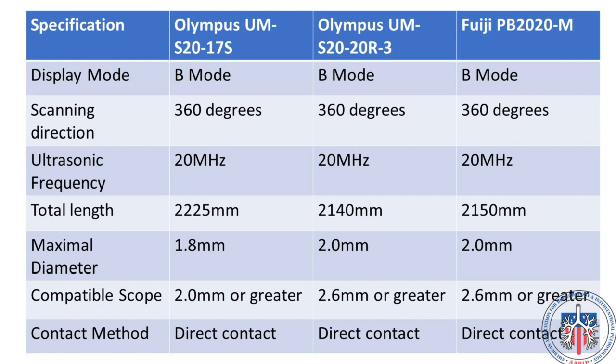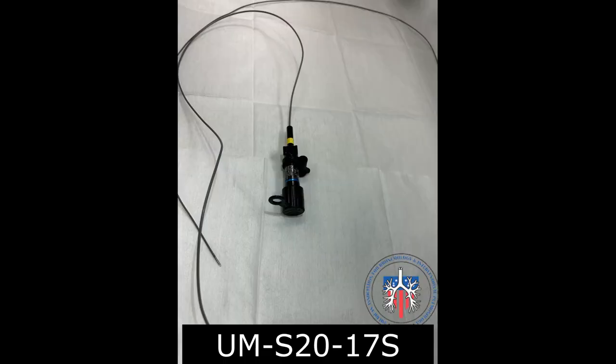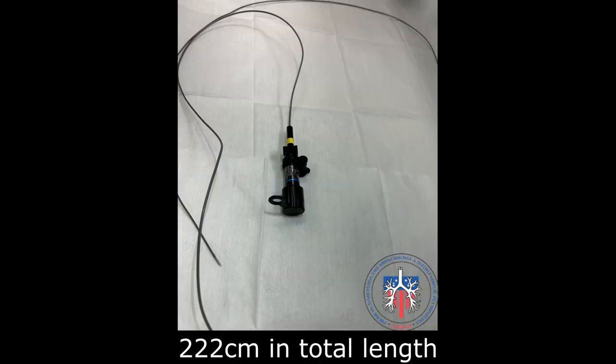All probes scan 360 degrees circumferentially in a perpendicular direction to probe insertion. They all have the same frequency, are similar in length, and use a direct contact method. This means that a balloon is not used on the end of the probe to make contact with the target lesion. For this video, the Olympus UM-S20-17S probe will be used.